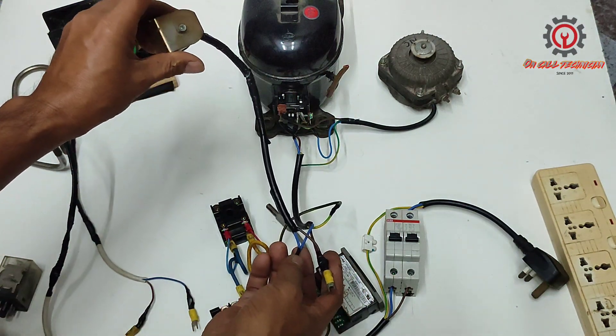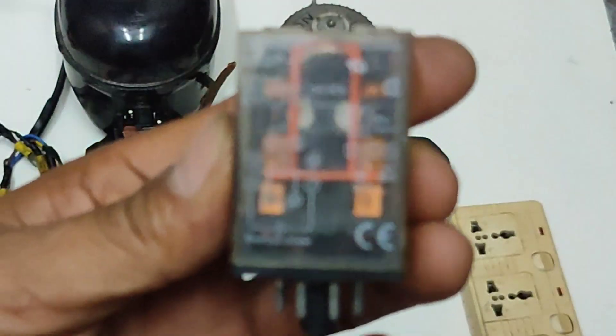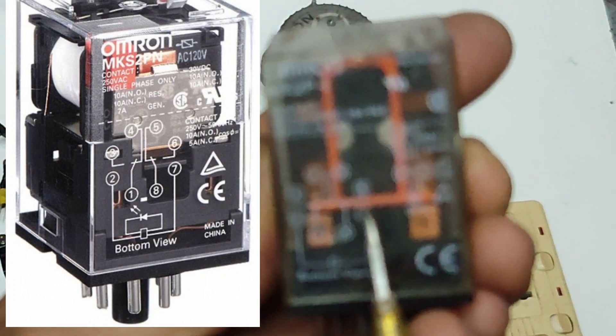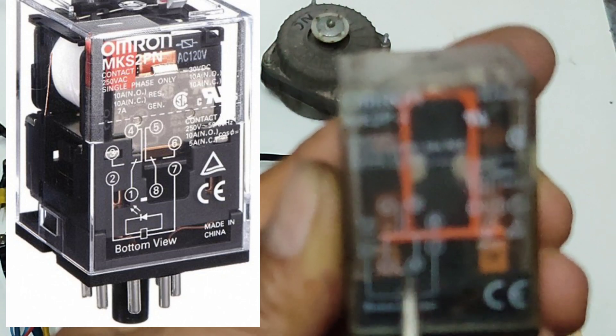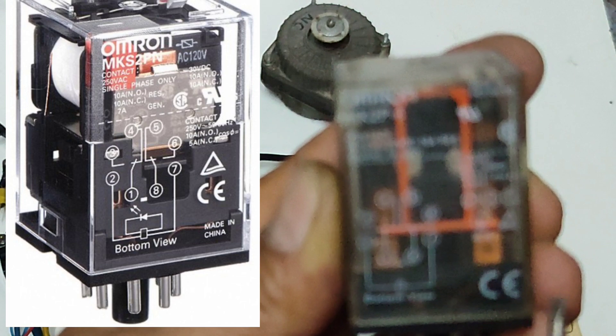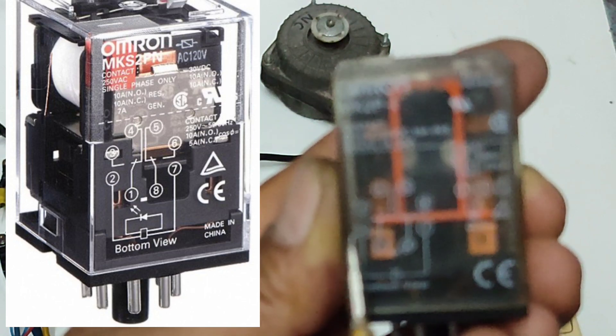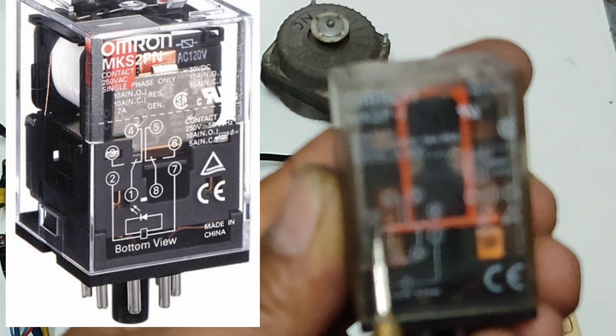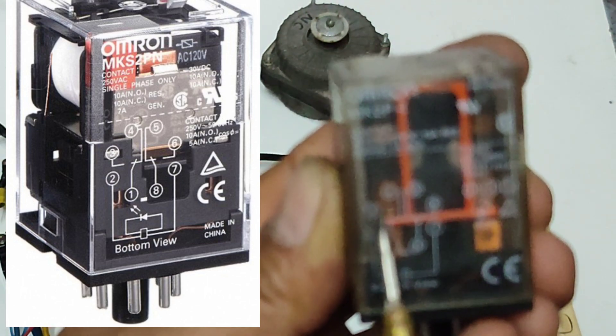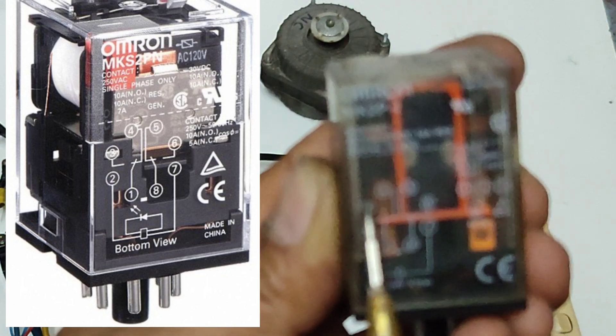Here is my relay. I hope you know the function of the relay. This is our coil — terminals two and seven for voltage. This will be the common here, and the normally closed is terminals four and five. And this side here is the normally open.